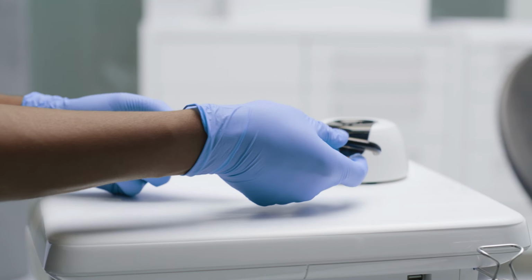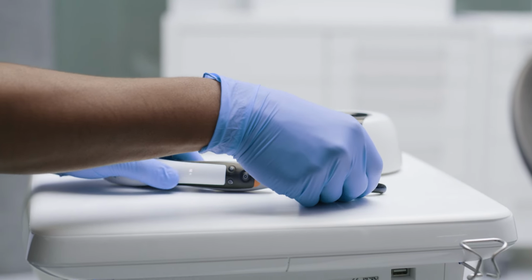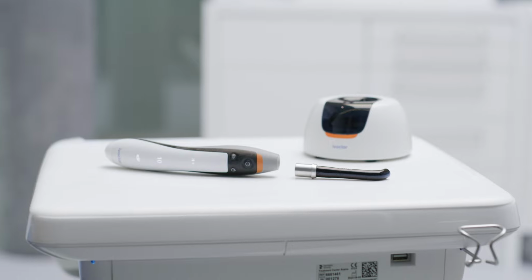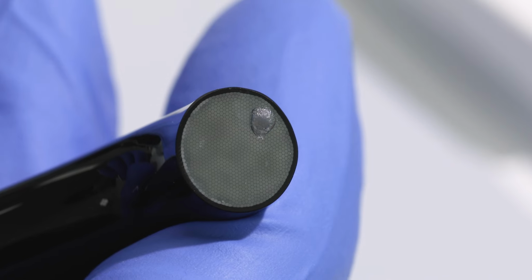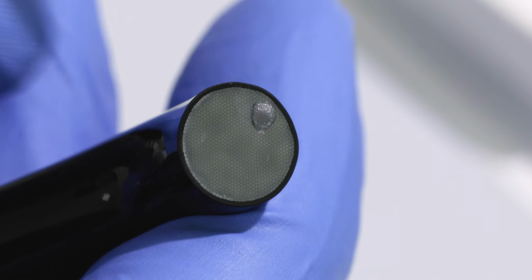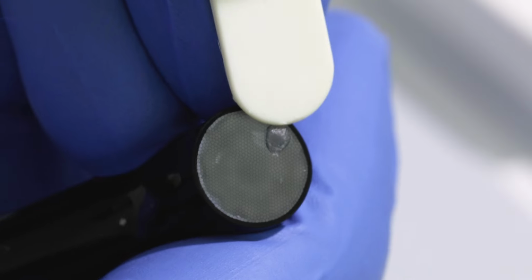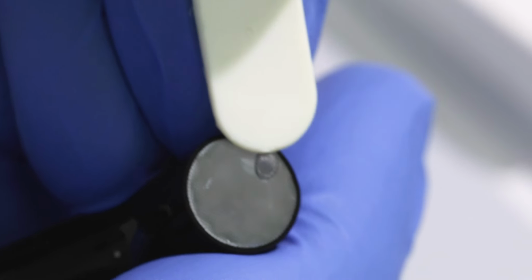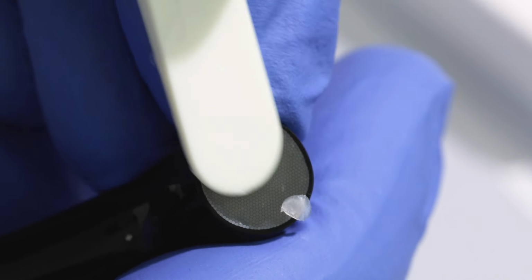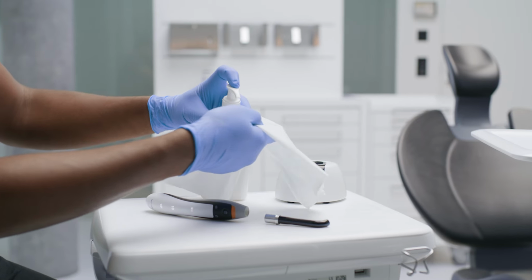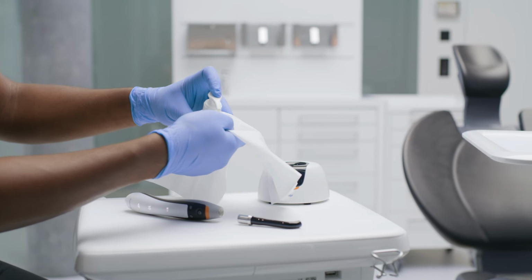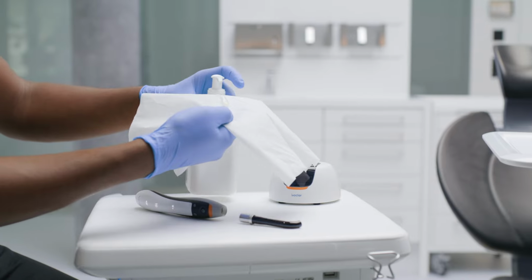After disinfecting the handpiece, we recommend removing the light guide from the housing, placing both horizontally and letting them dry for 1 minute. Partially polymerized composite can be removed with alcohol and a plastic spatula. Do not use sharp or pointed objects as they may scratch the surface. Especially dirty areas of the device can be cleaned with a soapy solution.